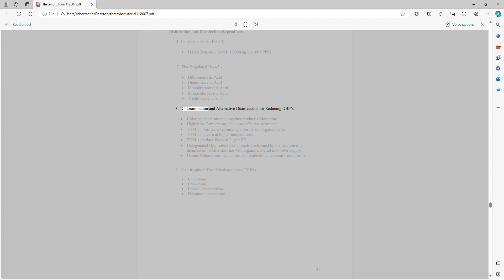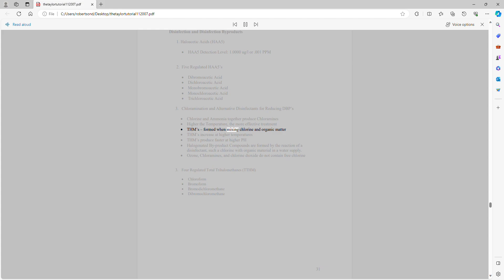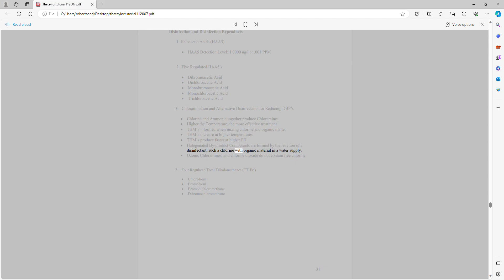Chloramination and alternative disinfectants for reducing DBPs: Chlorine and ammonia together produce chloramines. Higher temperature means more effective treatment. THMs are formed when mixing chlorine and organic matter. THMs increase at higher temperatures and form faster at higher pH. Halogenated byproduct compounds are formed by the reaction of a disinfectant such as chlorine with organic material in a water supply.